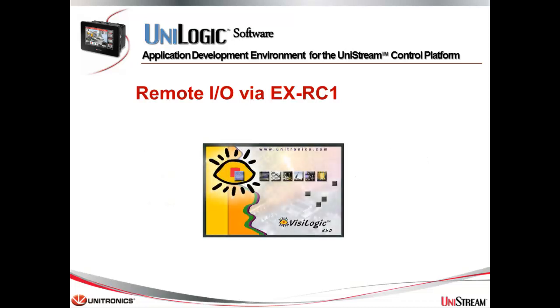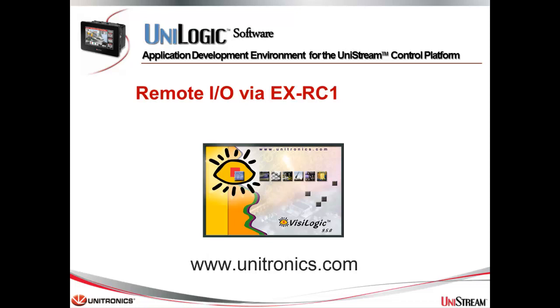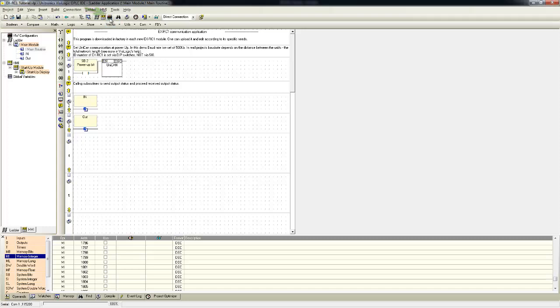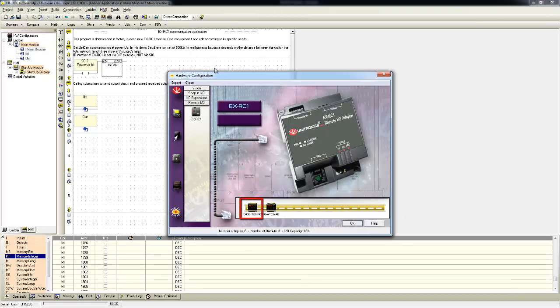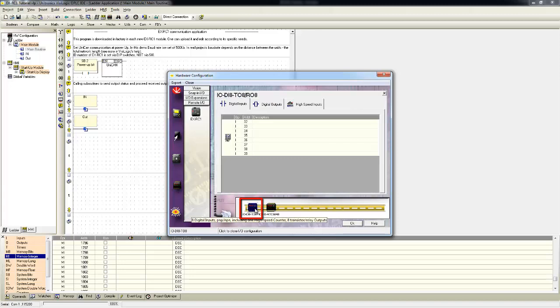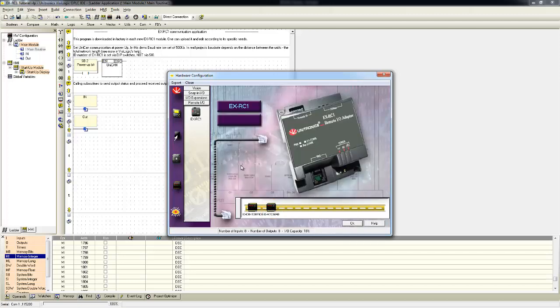The first step is to open VisiLogic, the programming environment for the vision series. You must use version 9.5 or later. VisiLogic can be freely downloaded from our website. I've already opened an example application of the EXRC1. In the hardware configuration, I configured I/O DI8-TO8, which includes eight digital inputs and eight digital outputs, and I/O ATC8 that has eight analog inputs or thermocouples. Now, we will export the entire EXRC1 hardware configuration to a file. We'll call it EXRC1HWC for hardware configuration.